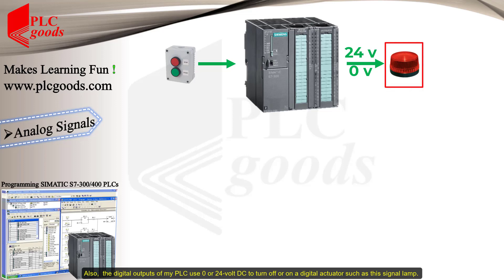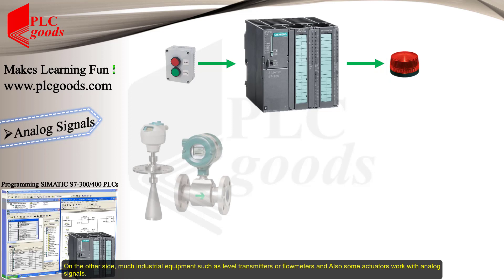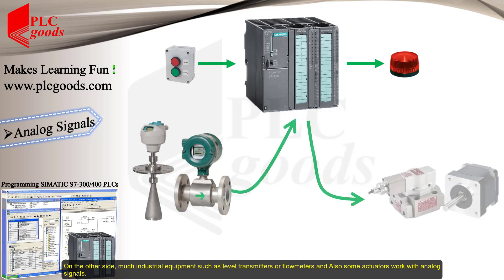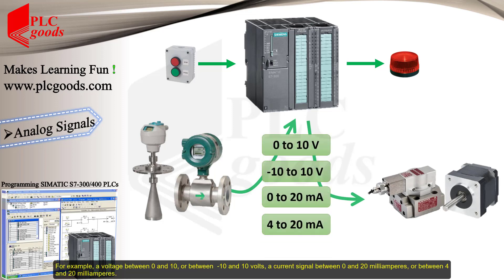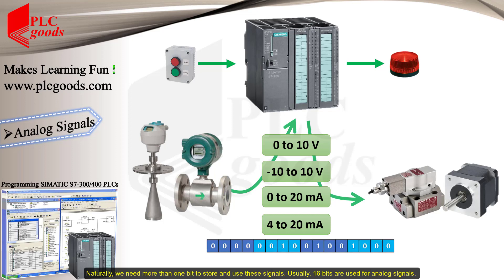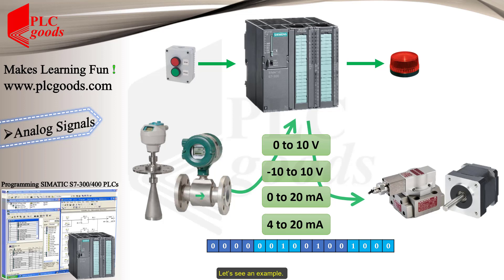On the other side, much industrial equipment such as level transmitters, flow meters, and also some actuators work with analog signals — for example, a voltage between 0 and 10, or between minus 10 and 10 volts, or a current signal between 0 and 20 milliamps, or between 4 and 20 milliamps. Naturally, we need more than one bit to store and use these signals; usually 16 bits are used for analog signals.